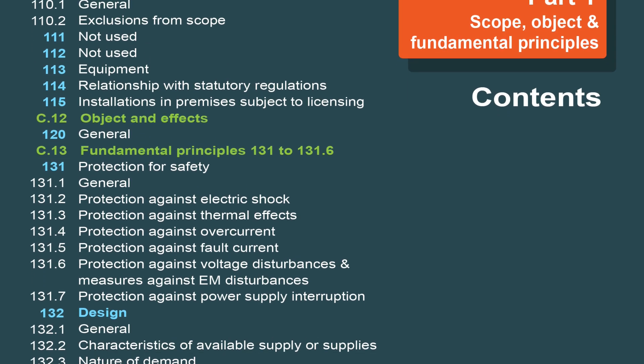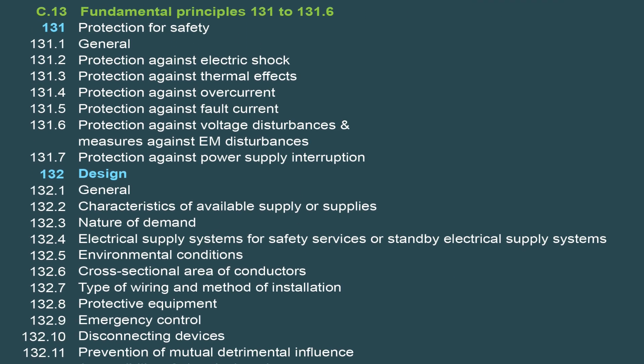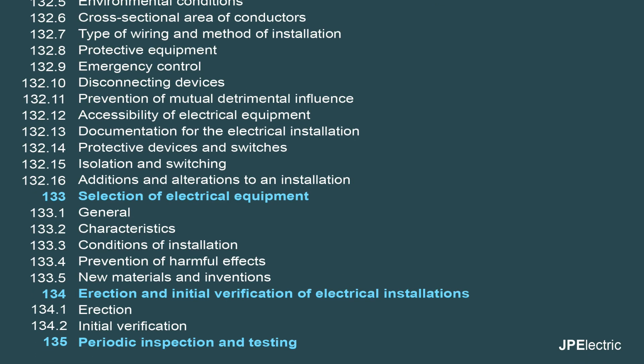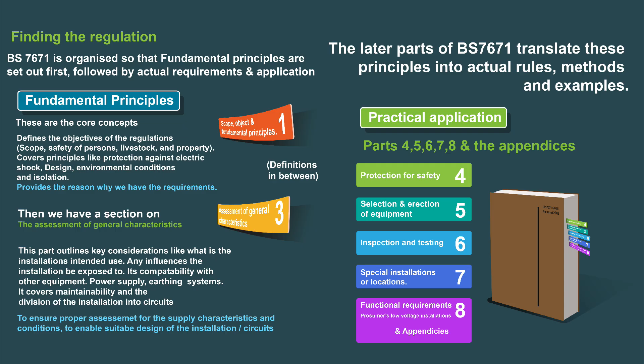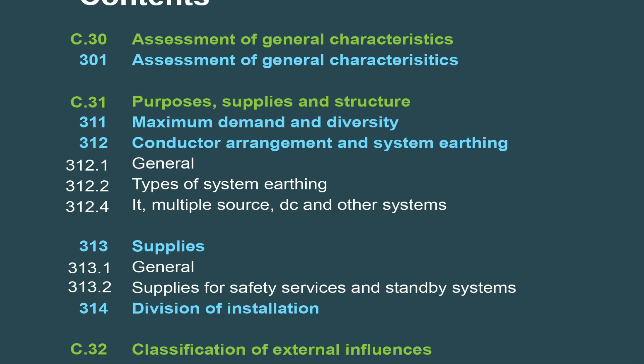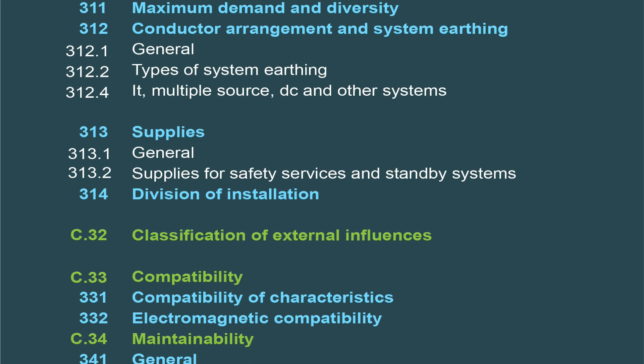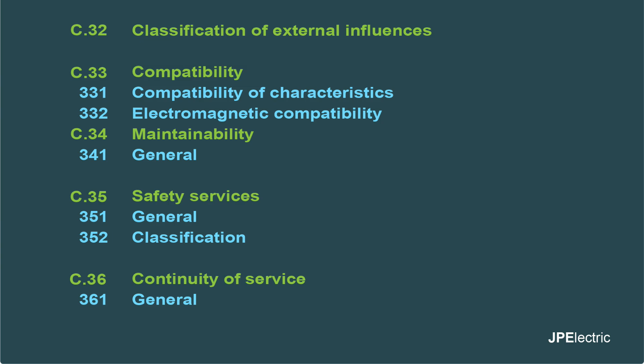BS 7671 is organised so that fundamental principles are set out first, followed by actual requirements and application. In part one — scope, objects and fundamental principles — these are the core concepts. It defines the objectives of the regulations: safety of persons and such, mentioning principles like protection against electric shock, design, environmental conditions and isolation, but it gives an overview only and doesn't go into detail. Then we have definitions, which is a descriptive list of the terms used in BS 7671. Then part three — assessment of the general characteristics — outlines key considerations like the installation's intended use, influences the installation might be exposed to, compatibility with other equipment and services, power supplies, earthing systems, and the division of the installation into circuits.